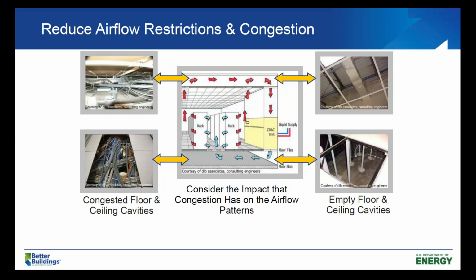All right, so restrictions and congestion. So again, good air management is about getting the air to go where you want and not where you don't. And if you block the airflow where you want it to go, then it can't get to where it needs to go. And so on the left is an example of congested floor and ceiling cavities packed full of cables, probably a lot of which are no longer in use. And on the right is a much better example of those spaces that then enables the air to flow freely where it should. Next slide.